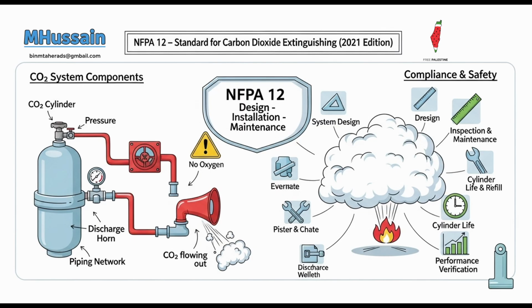The main supply must be sufficient for the largest single hazard protected, enough for the biggest risk, or for a group of hazards that are designed to be protected simultaneously. If continuous protection is required, meaning the hazard needs to be protected even after an initial discharge, perhaps for a potential reflash, a reserve supply is also mandated. Main supply and a backup reserve.